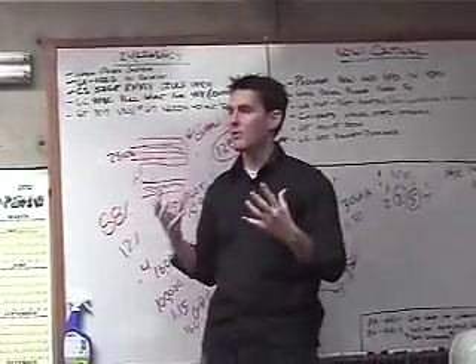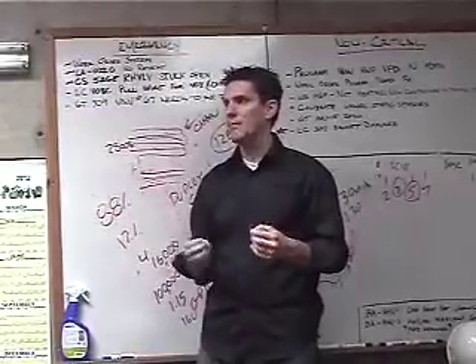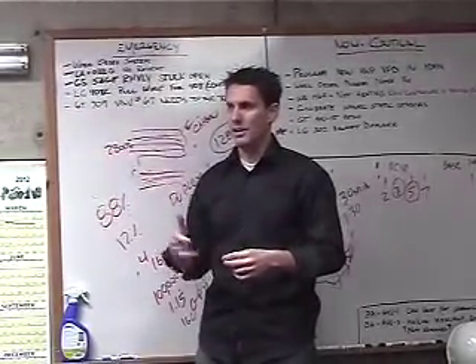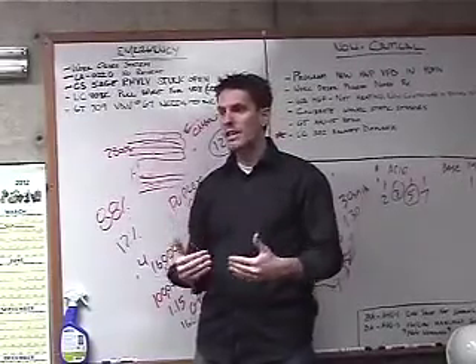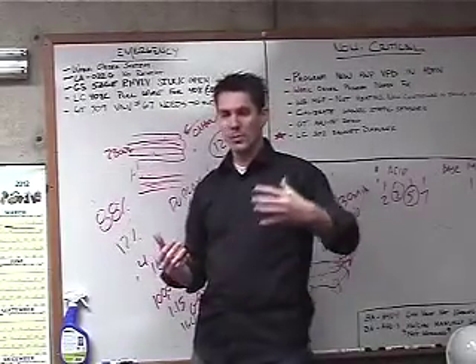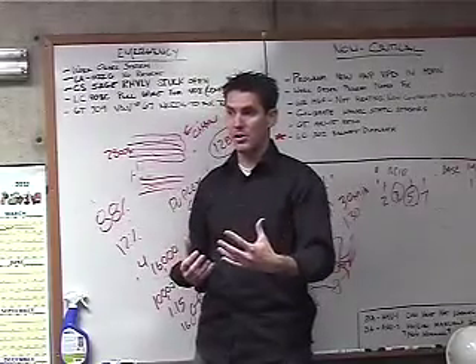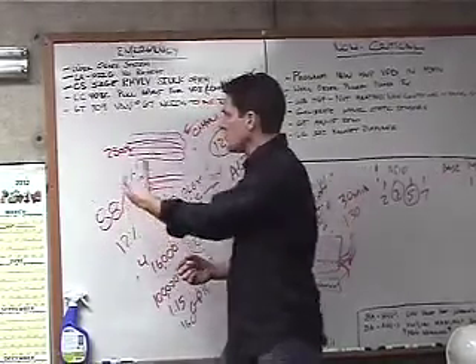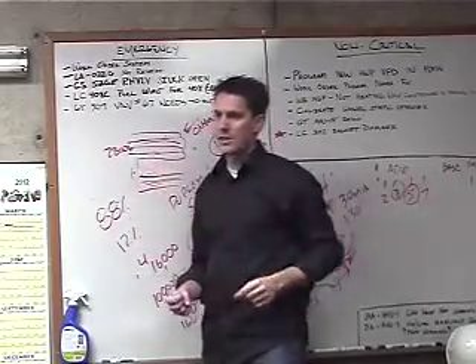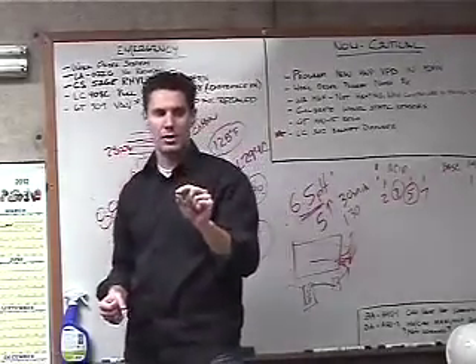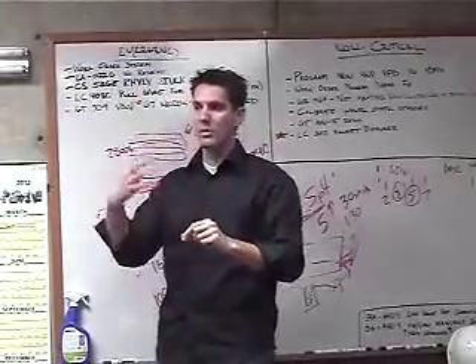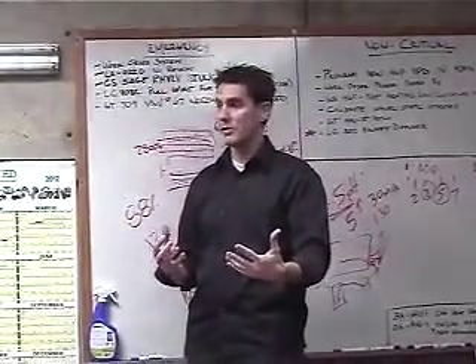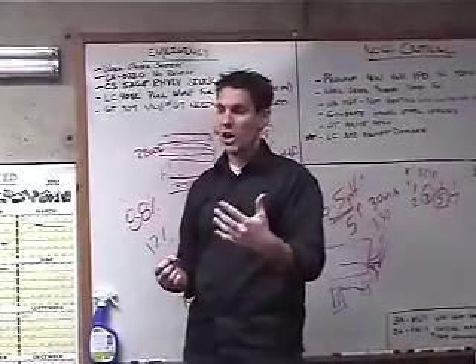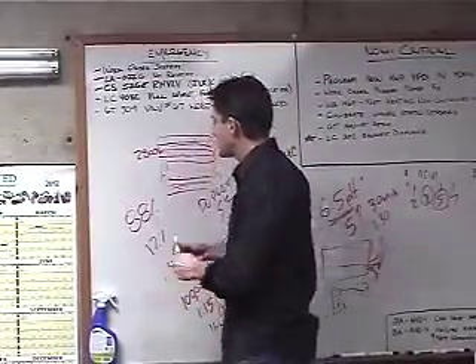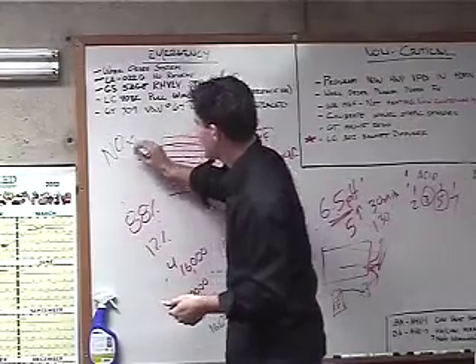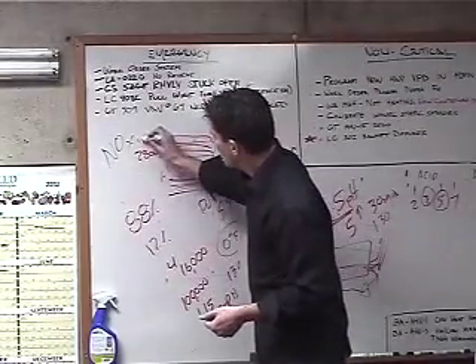Okay? Because most of the air that we breathe, 79 or 78% of the air we breathe is what? Nitrogen, not oxygen. We don't need nitrogen for combustion. We need oxygen. So we're putting all this air in for the process of combustion, but we're feeding a lot of nitrogen. With extremely hot flame temperatures, if I exceed 2,800 degrees, something's going to happen with that nitrogen and the oxygen, that O2 that we've got in there and the nitrogen. You guys ever heard of NOx? Okay. NOx, N-O-X. NOx is not one compound. The reason it's an X is the X is a variable from 1 to 7.